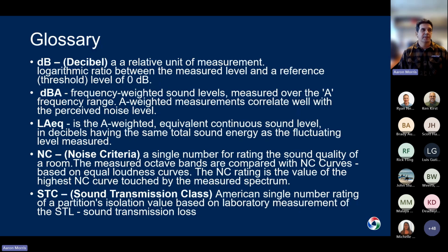NC stands for noise criteria, which is a common way of referring to sound requirements in a room. The NC curves have also been developed to focus on the octave bands that are best perceived by us. And the way that works is if any octave band measured value goes above that curve, you don't meet that NC level.